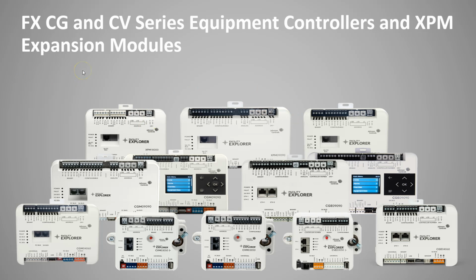They never show up. All you see is extra points under that controller, okay? But all three of these expansion modules can actually be BACnet devices on a BACnet trunk. So they're either or. You could program them to be on the SA bus of a controller, or you can program them to live on a trunk.